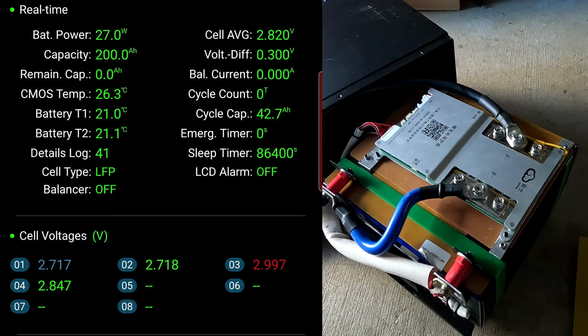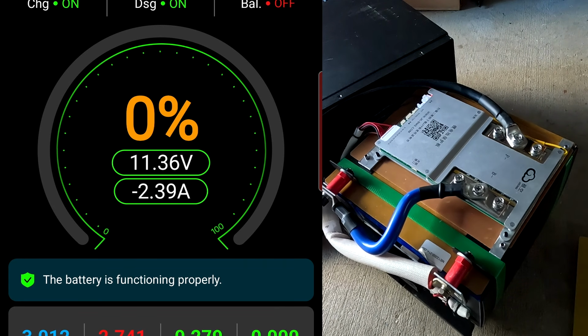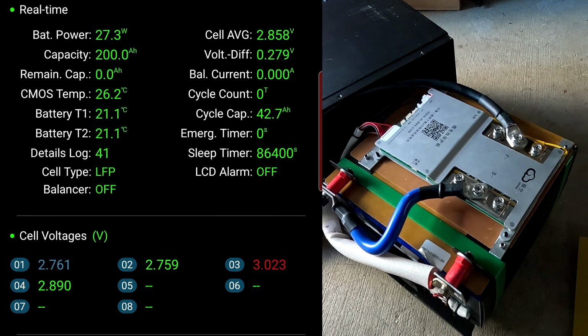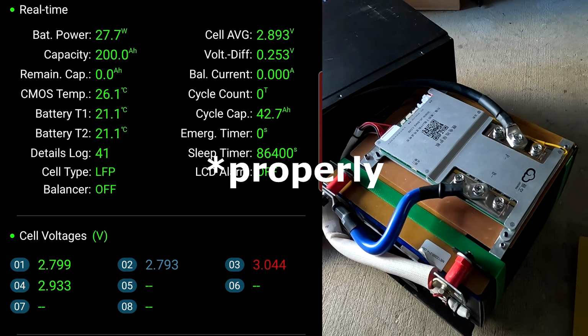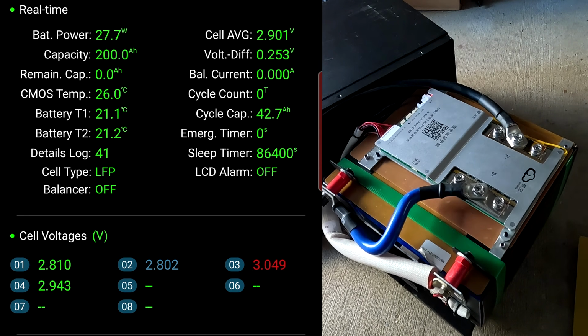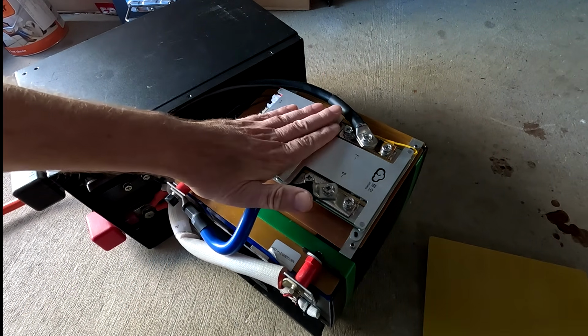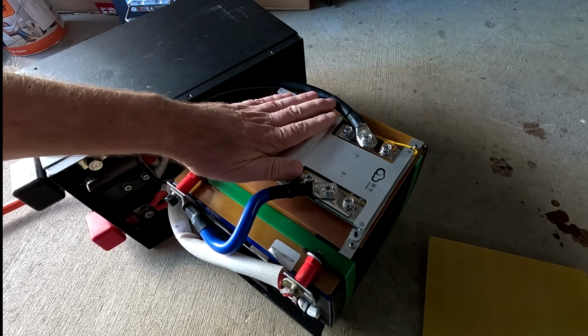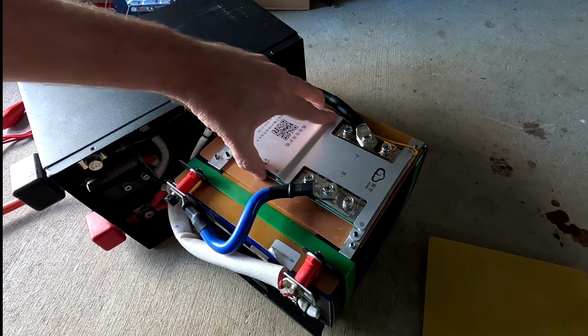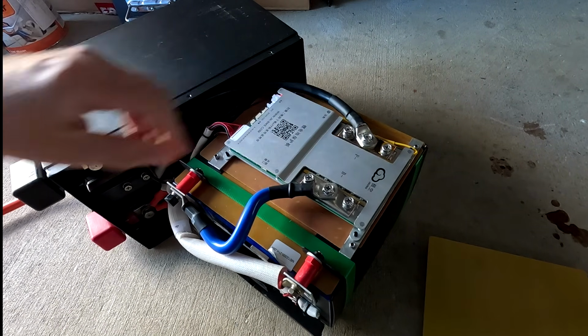One of the cells has hit 2 volts. Actually, the inverter has shut down because we've got a cell deviation of 280 millivolts, which is quite high, but the battery hasn't been properly top-balanced for quite a while. The Daly BMS does not balance anything, and the active balancer inside did more damage than good. So we have to fully charge this battery, fully top-balance it, and see what's going on. But so far I'm pretty happy with the performance and result, there are no thermal hotspots, no heat issues, nothing like that, so this is all good and working perfectly fine.